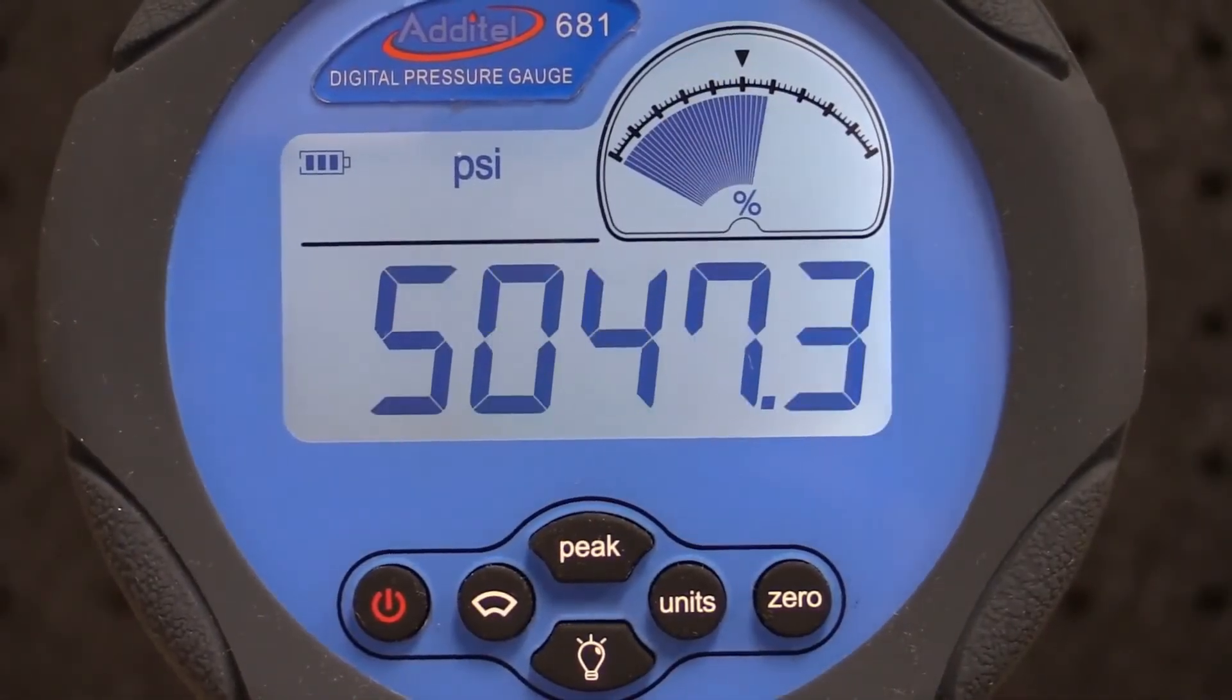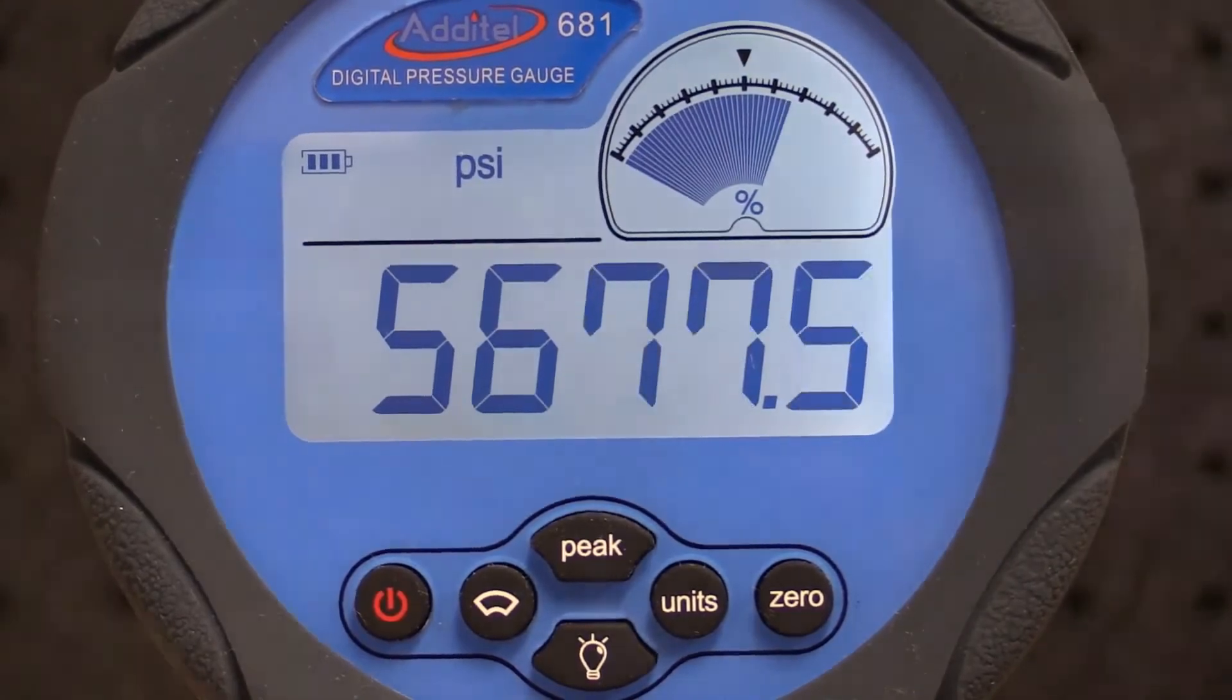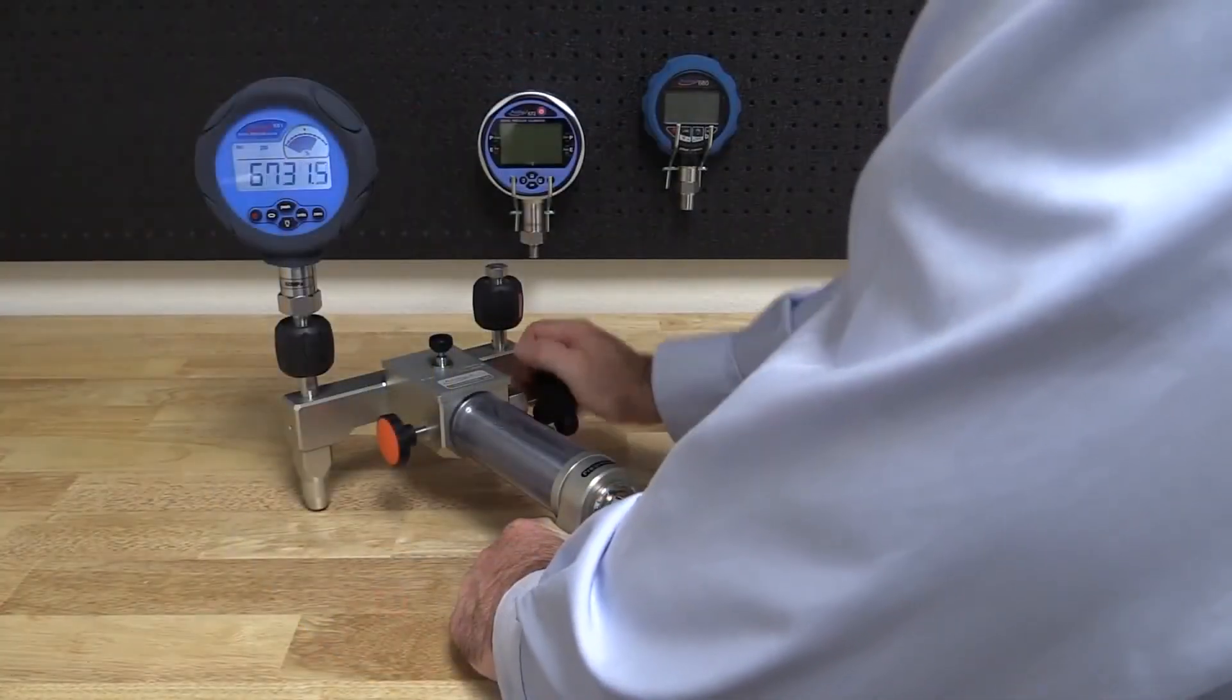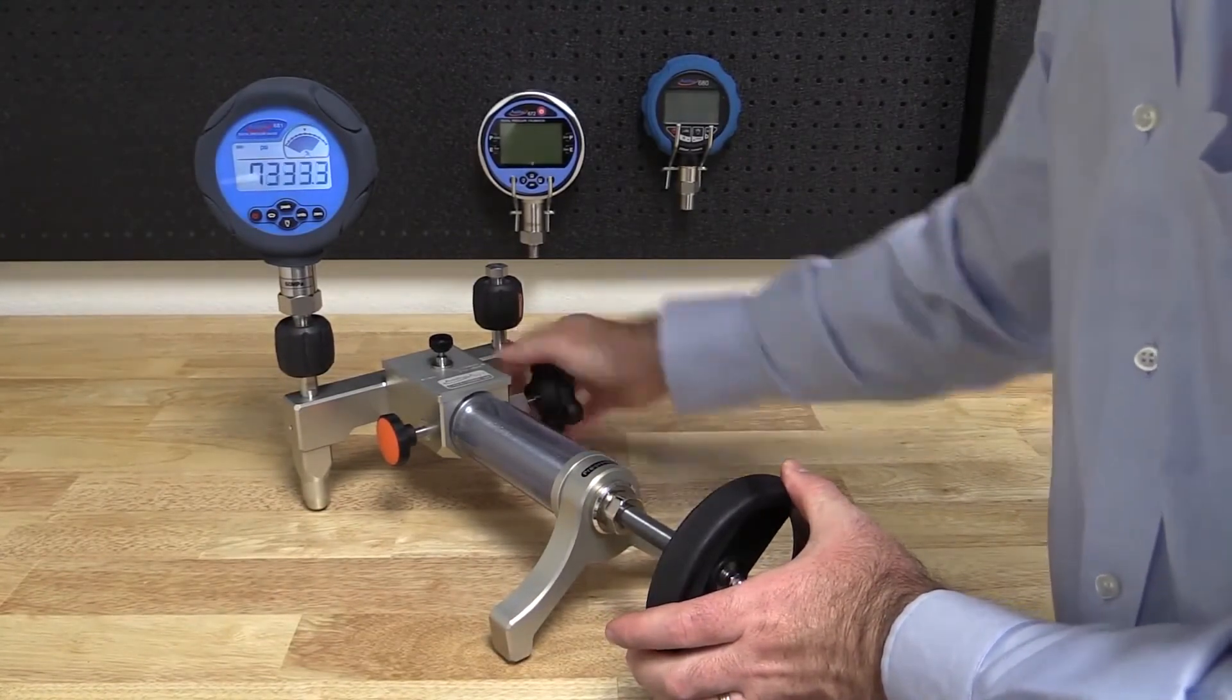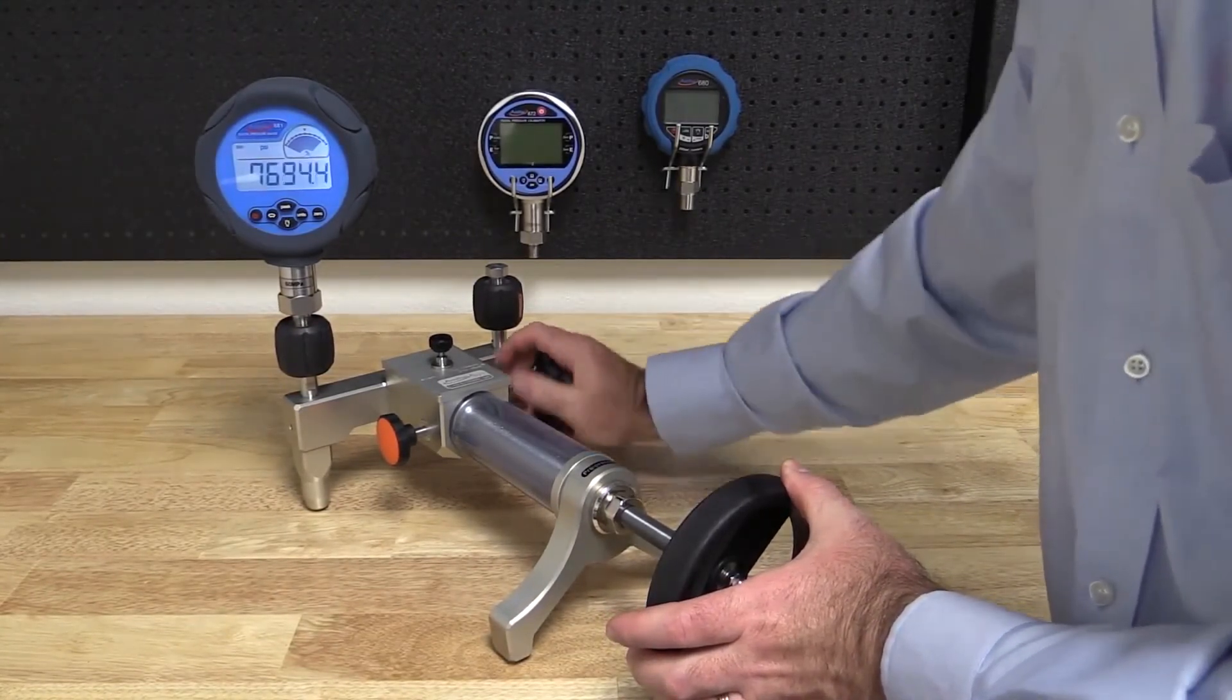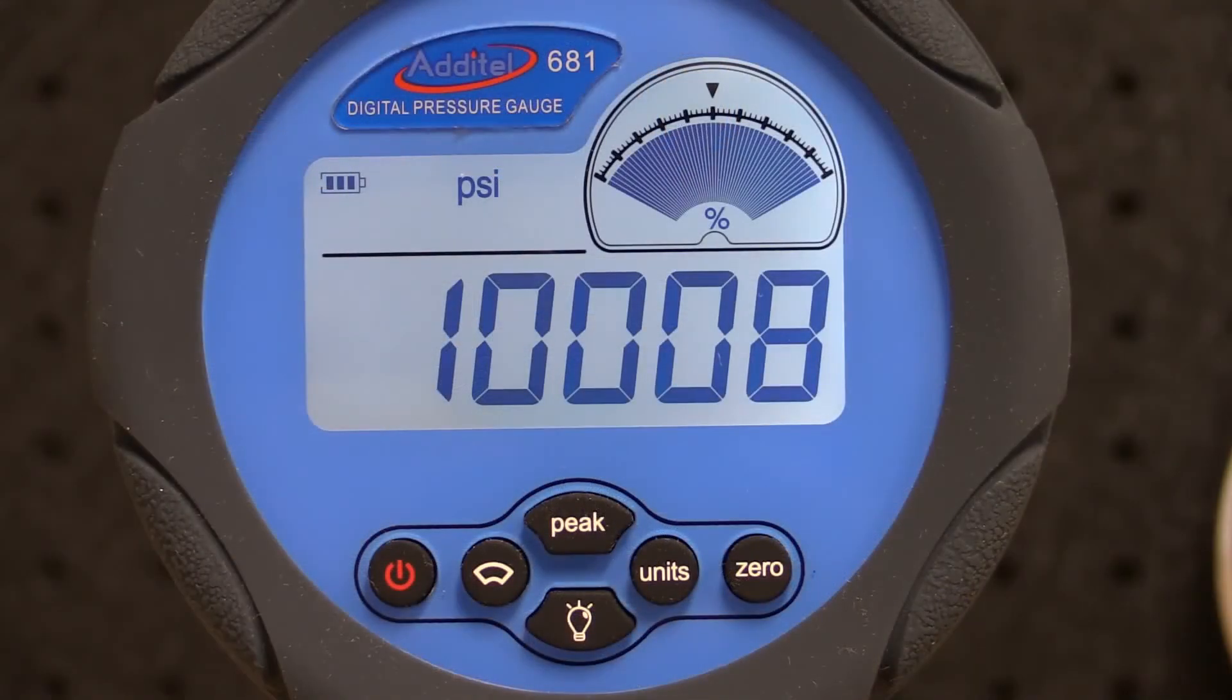For higher pressures, we need to use the high pressure or fine adjustment knob to generate the remaining pressures and dial into a cardinal point. At the high pressures, it may take a few minutes for the measurement to stabilize. Small adjustments using the fine adjustment knob may be needed to ensure that you achieve the cardinal point.